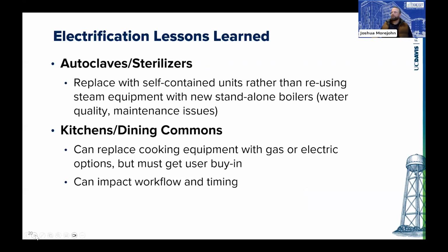Last one I want to touch on is just, well, two really. One is when you're going through buildings, we have a lot of lab buildings with autoclaves and sterilizers. We've found that having self-contained autoclaves and sterilizers with their own generation, instead of a standalone boiler to serve them, is often a much more effective approach. It's kind of a specific one, but in case it applies, it gets away from having to deal with water quality and maintenance issues with the boiler system you'd be putting in.